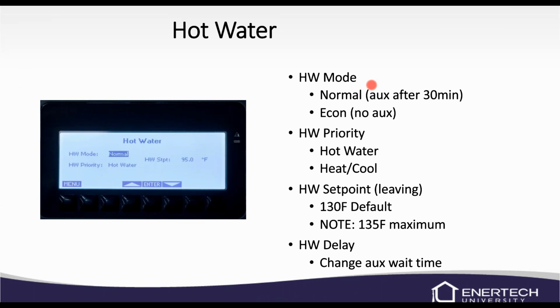Hot water mode, normal, auxiliary after 30 minutes, or no auxiliary. Priority, you can do heating or cooling, so that's hydronic, heating or cooling, or your domestic hot water. My take on it is I would rather have a hot shower than a warm floor. So I would choose hot water as my priority all the time, but that's totally up to you. Your hot water set point on your leaving, 130 is default, 135 is max. I see that the majority of the time about 125. And then we also have a hot water delay as well. It's not showing here on the screen, but we can change that.